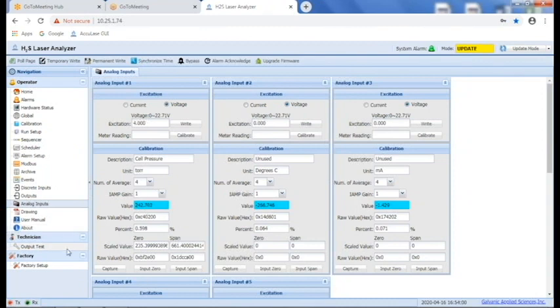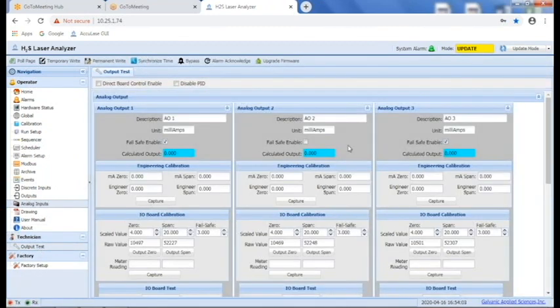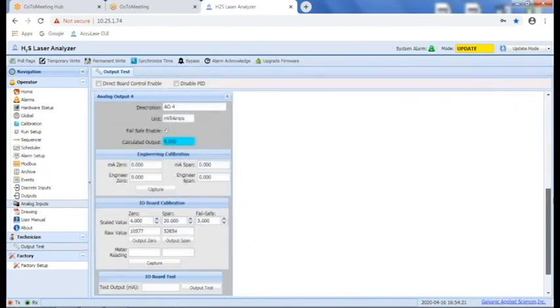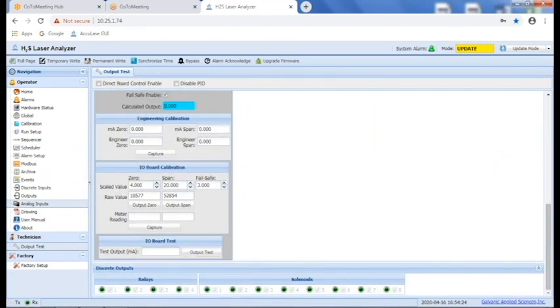And then there are links to some drawings, the user manual, and some other information. There's an output test here, which allows you to basically fire your loops if you want to. For the outputs, you can set a pre-programmed value, and you can do the same thing for your relay outputs at the bottom, and you can fire them. To do that, you need to use this command called direct board control. Basically, that takes the control away from the analyzer and gives it to the user.